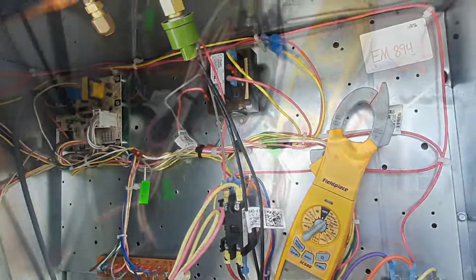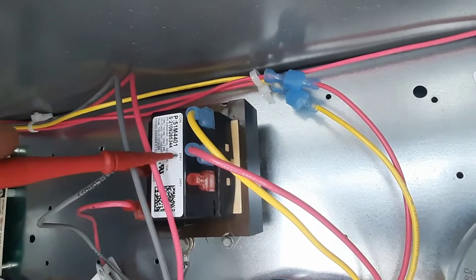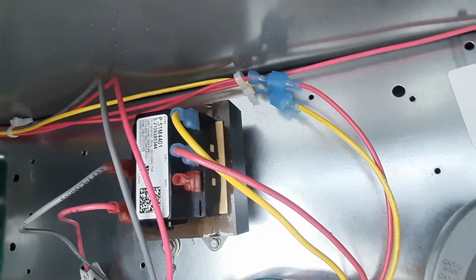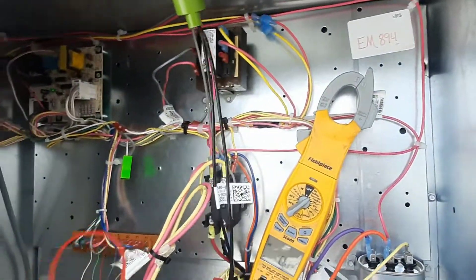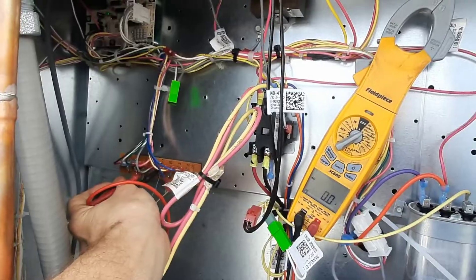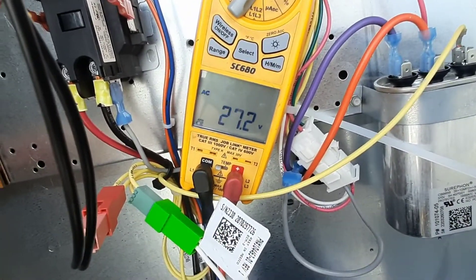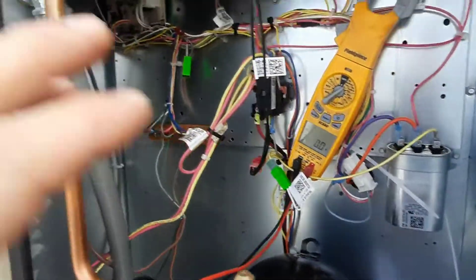You can see we are now tapped to the 208 spot, and that's going to match our actual voltage. We're going to have more like 27 volts — and you can see, 27 volts.